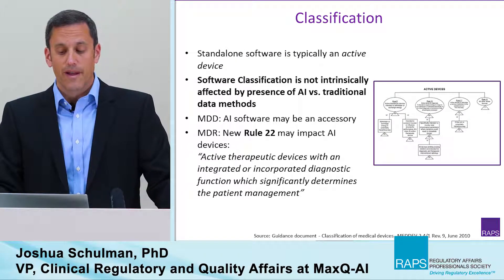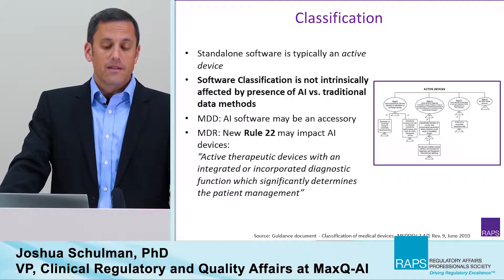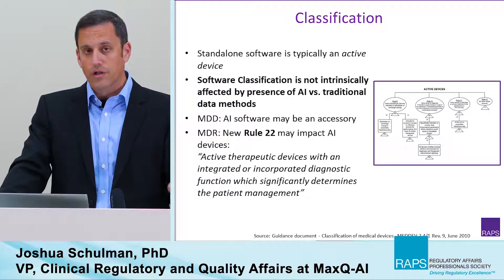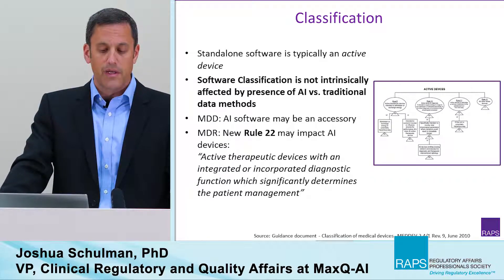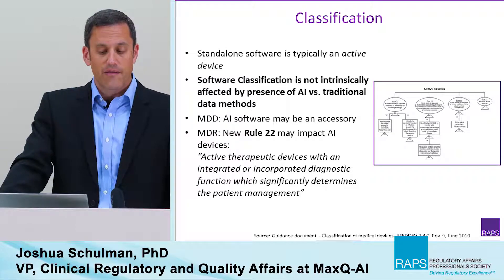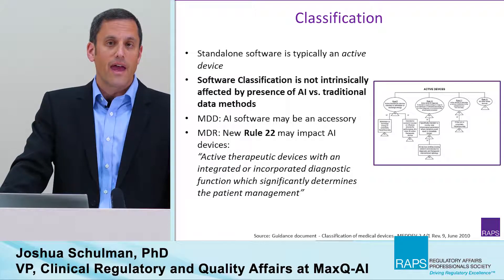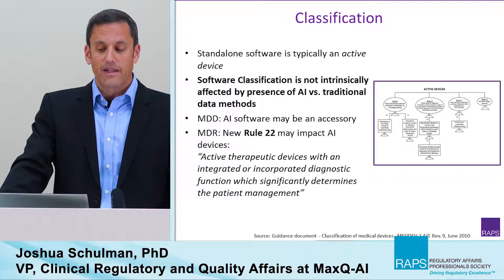Assuming a piece of software is a medical device, the next step is classification. Standalone software is typically considered an active device under the MDD. It's interesting to note that software classification isn't intrinsically affected by the presence of AI versus traditional data methods in either the MDD or the MDR. In the MDD, it's more likely to be an accessory. However, in the MDR, there's a new rule — Rule 22 — which may impact AI devices. That rule covers active therapeutic devices with an integrated or incorporated diagnostic function which significantly determines patient management. That may mean that a lot of AI devices, which under the MDD may not have been considered medical devices, are now considered devices.